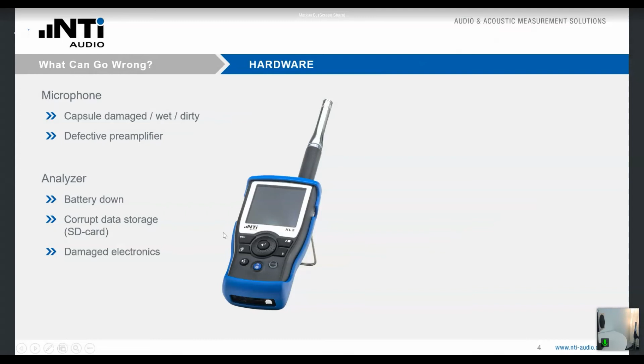So what can we do to avoid, or to at least identify such problems in order to avoid them? Well, the key approach, the most efficient approach, is that you verify the microphone sensitivity with a microphone calibrator. I will show you that later in a practical presentation. But by doing so, you will be very safe that the whole signal chain, all the elements, the microphone and the instrument itself, which are involved in the signal processing, are operating correctly. So this is really the most popular, the most important approach to avoid any hidden problems.